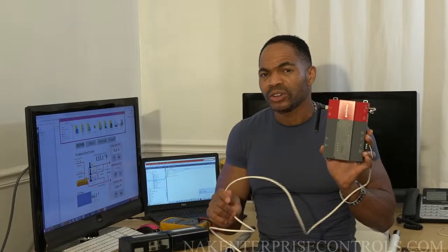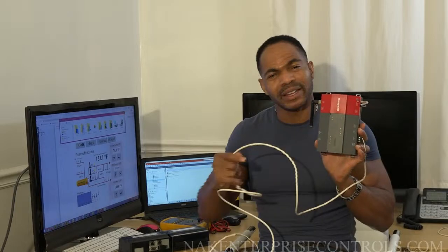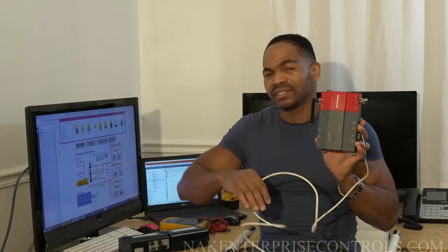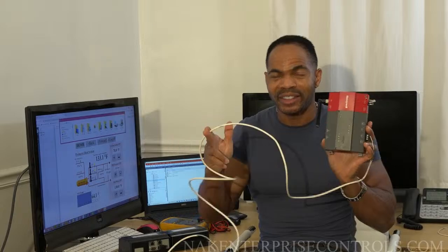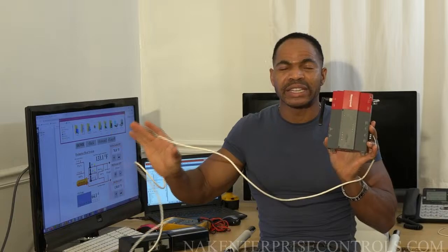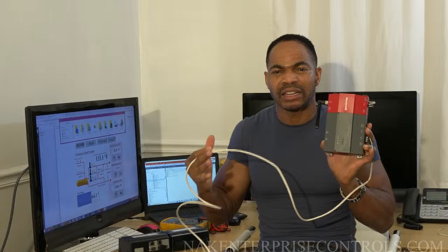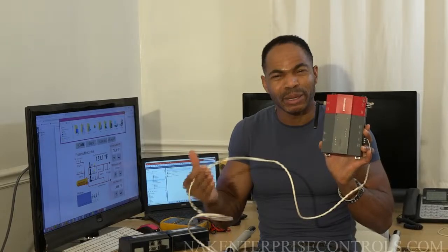So it is wise that you keep IO a bit closer to your Jace. Someone, as you know, cuts your MSTP, the unit that IO is serving is going down. The IO doesn't retain any memory. So that would be one of the drawbacks.